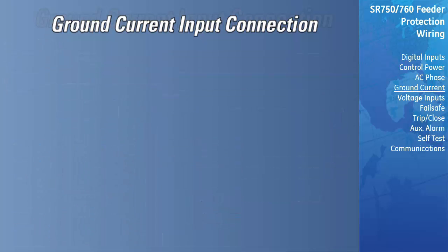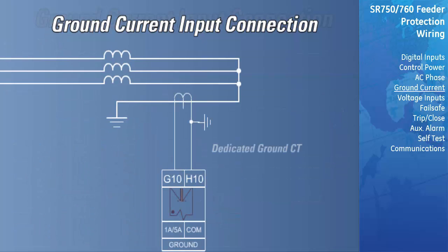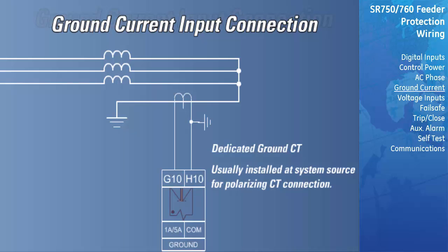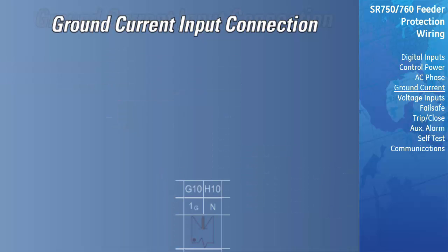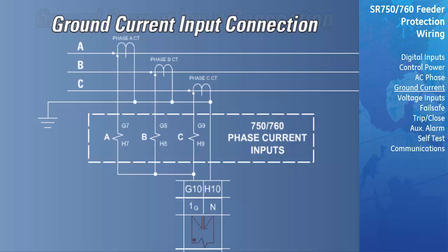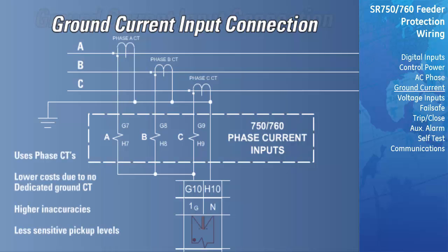The first is a dedicated ground CT installed on the neutral of the system. This connection is generally used at the system source for polarized ground connections. The second is a residual ground connection. This reduces the cost of implementing ground protection, but it increases the error in the system due to the accuracy limitations of the three-phase CTs. Pickup levels will need to be set higher with this CT configuration.